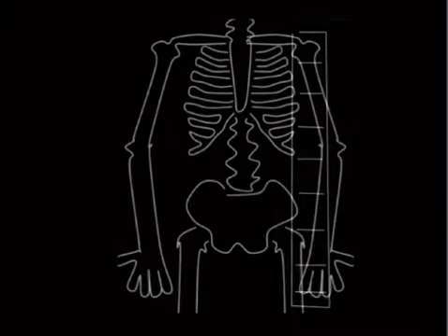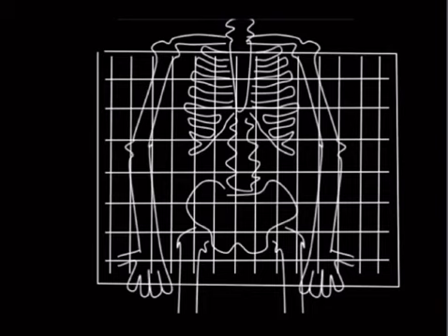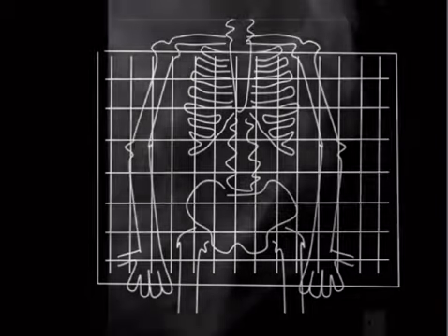So why don't you see grid lines like this? This is a mammogram. We'll zoom in so you can see it. Note the lines here. Why does that happen? That's a type of artifact. Basically, when you've got a Bucky grid, it moves back and forth like this.